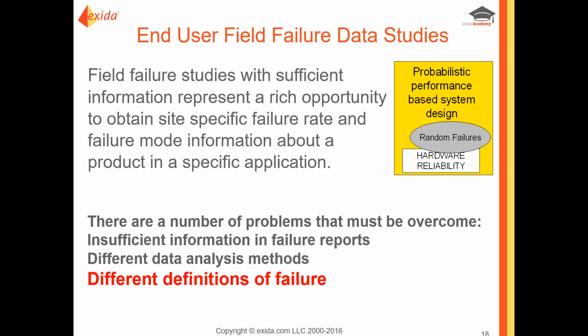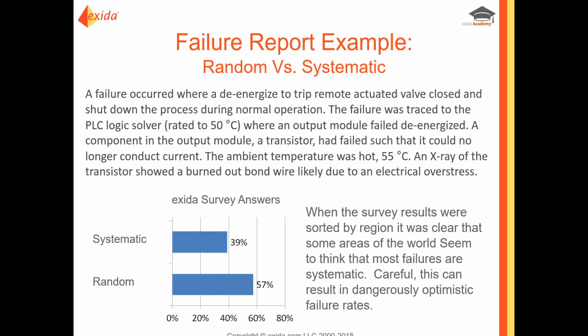In many of the sets of reports that exida has been hired to analyze, we've discovered there's a lot of missing information that would have been valuable, that would have made the information set more valuable. We found different data analysis methods being used, some of which were optimistic and some of which were somewhat pessimistic. But perhaps the biggest issue of all is the definition of a failure. It's inconsistently applied.